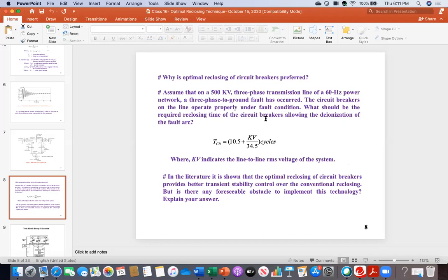Everybody read this in the middle, there is a numerical problem. Assume that on a 500 kV three-phase transmission line of a 60 Hz power network, a three-phase to ground fault has occurred. The circuit breakers on the line operate properly under fault condition. So, pretty good. What should be the required reclosing time of the circuit breakers, allowing the deionization of the fault arc? Like I was telling you, the arc extinguishing is basically deionization. As long as there is arc, it is called the ionization form. Then you have to deionize, allowing the deionization of the fault arc. Here kV indicates the line-to-line RMS voltage of the system. So can you tell me what should be the required reclosing time?